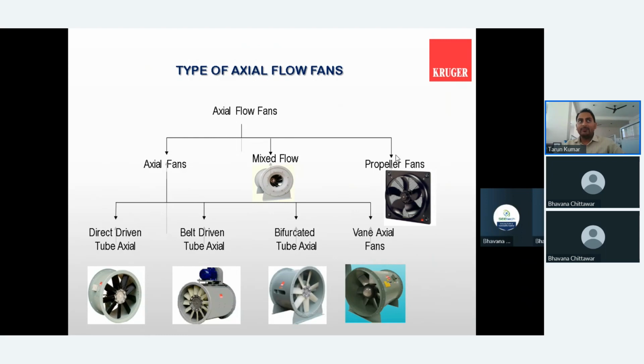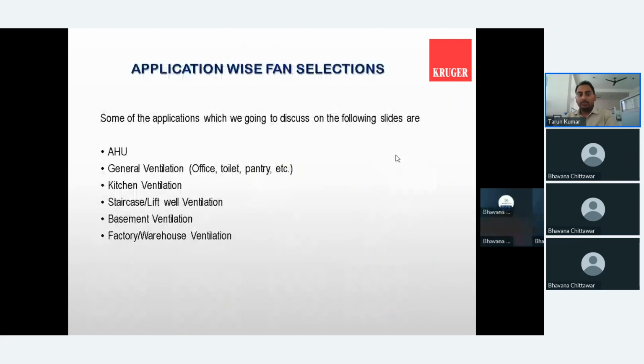So basically the major difference between centrifugal and axial fan is that the axial fan is known for higher volume, whereas the centrifugal fan is used for higher volume as well as higher static pressure. So whenever our application is for higher volume, we should directly go with the axial fan. At the same time, when your static is also high along with your CFM, then we should select the centrifugal fan.